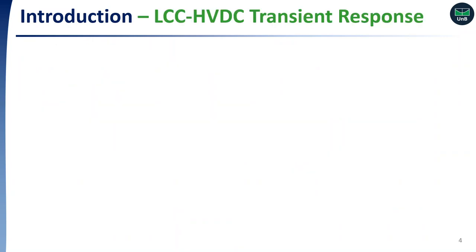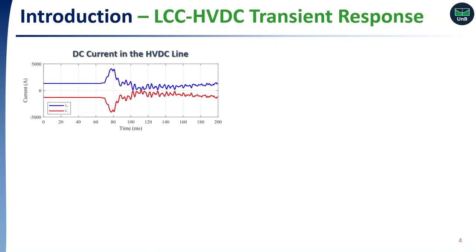Aiming to understand the problem better, let's see an example of the transient performance of LCC-HVDC links during AC faults taking place nearby. These are the DC currents in a bipolar system. As one can see, converters' responses lead to quite distorted DC currents after the AC fault takes place. During this time, commutation failures may occur.